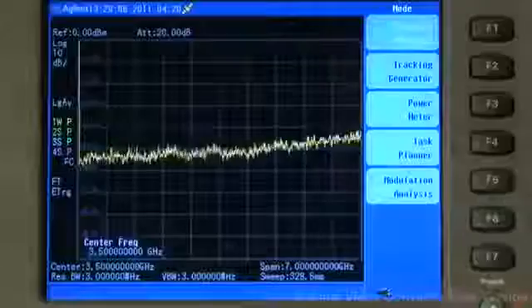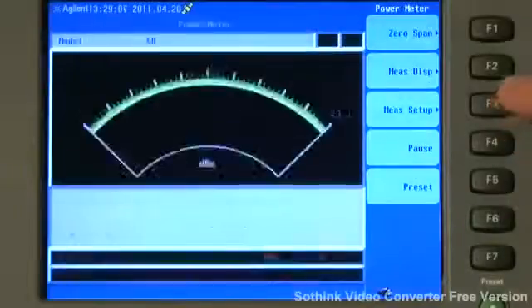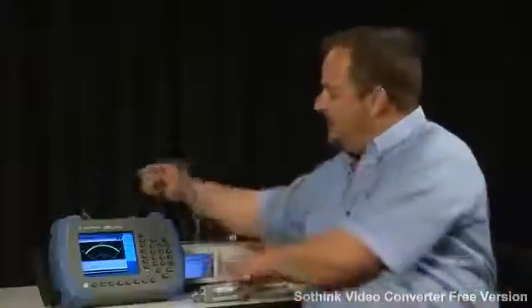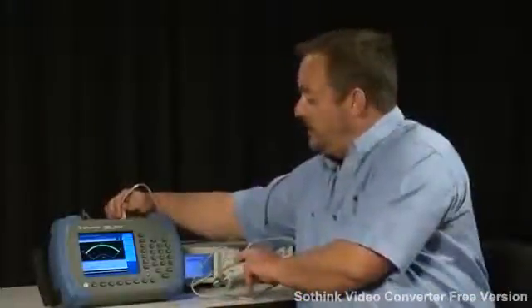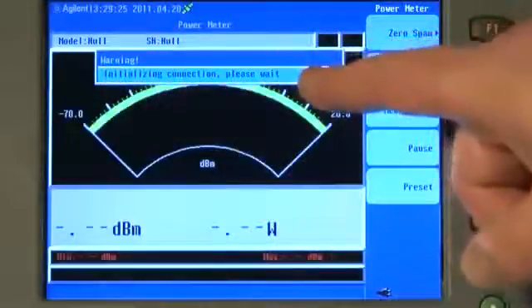But you can also plug them directly into Agilent's handheld spectrum analyzers. We just press the Mode key and select Power Meter. And I'll plug the USB lead into the USB port on the analyzer. You'll see the power sensor has been recognized and is initializing.